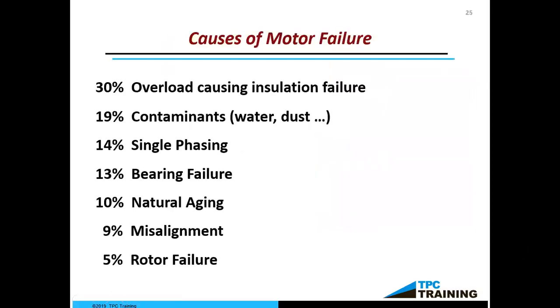So here's some causes of motor failure. And we can see right off the bat that we overloaded the motor, and it created a lot of heat when we overloaded the motor because it was drawing more current, and it caused my insulation to fail. And that insulation, of course, would be on the stator windings. And when it failed, you know, we would develop a short circuit. So the megger could help us determine when this could happen.